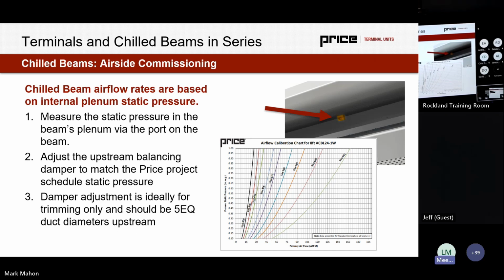So the question was, can we use DCV with chilled beams, or does it kill the induction rate when we get too low at nozzles? And we absolutely can use demand control ventilation with a beam. We just have to be cognizant of what our design turn down ratio actually is going to be.